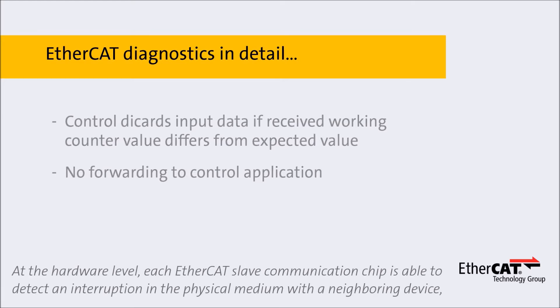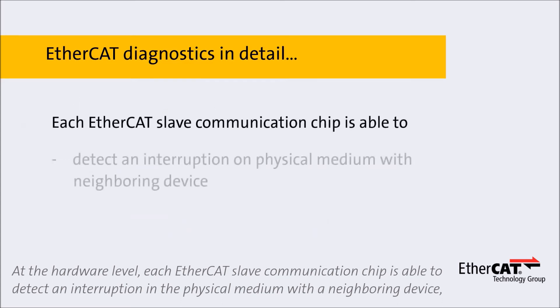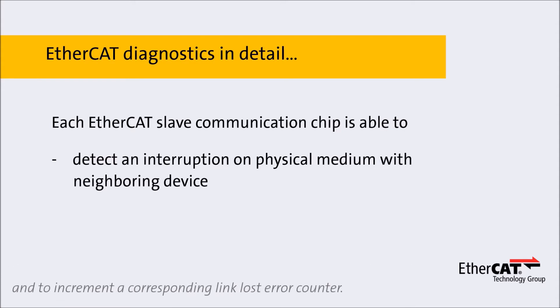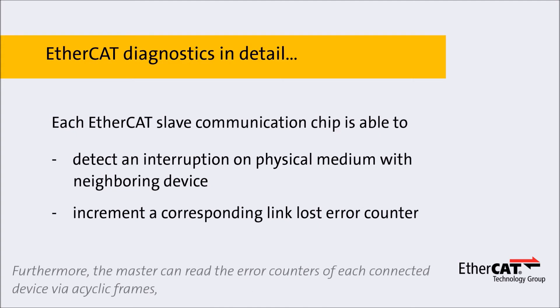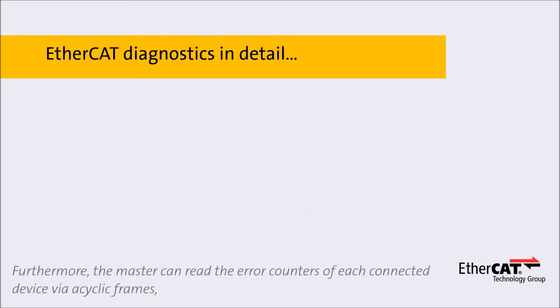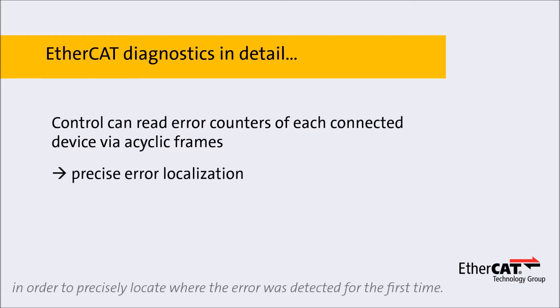At the hardware level, each EtherCAT slave communication chip is able to detect an interruption in the physical medium with a neighboring device and to increment a corresponding link lost error counter. Furthermore, the master can read the error counters of each connected device via acyclic frames in order to precisely locate where the error was detected for the first time.